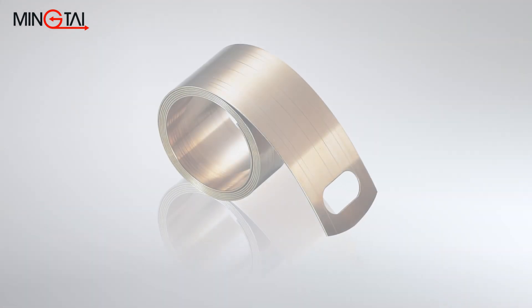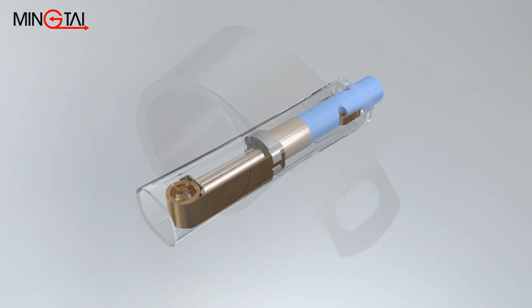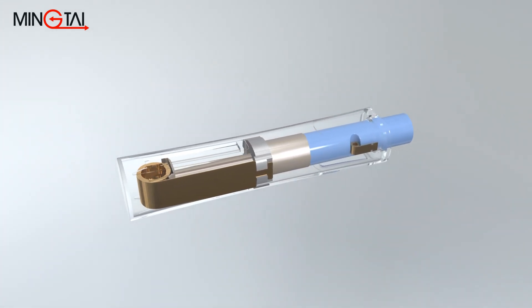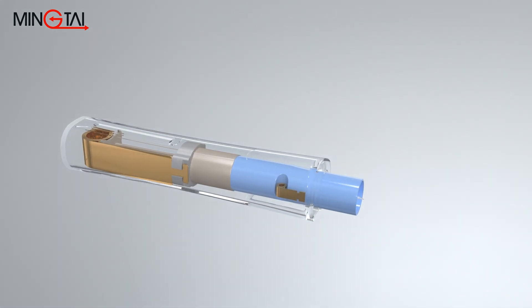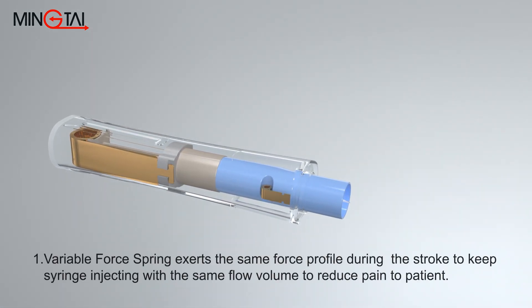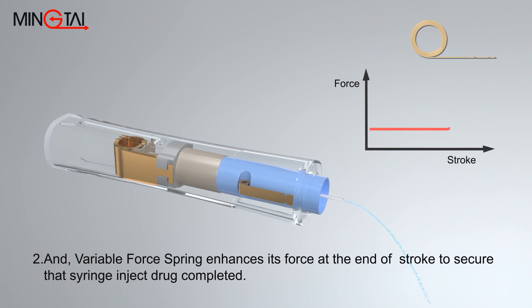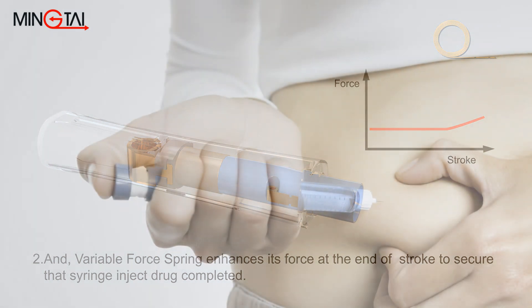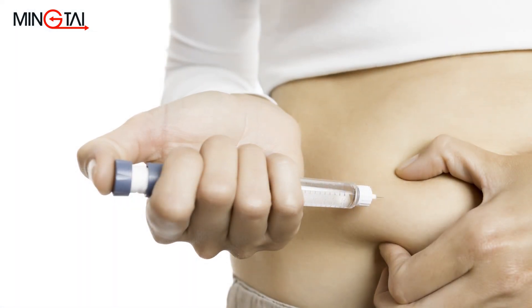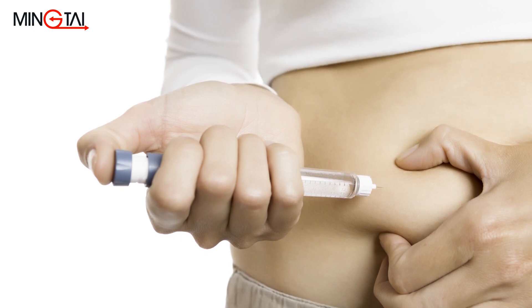Constant force springs can also be applied to precision pen-type drug injectors. They feature unprecedented repeatability for a system that can consistently and accurately produce extremely short plunger movements with a maximum displacement variation of plus or minus 0.026 millimeters, which is less than half the width of a human hair. A compact and easy-to-use precision pen injector utilizing a constant force spring is an excellent replacement for a traditional syringe where accuracy can be difficult to control.